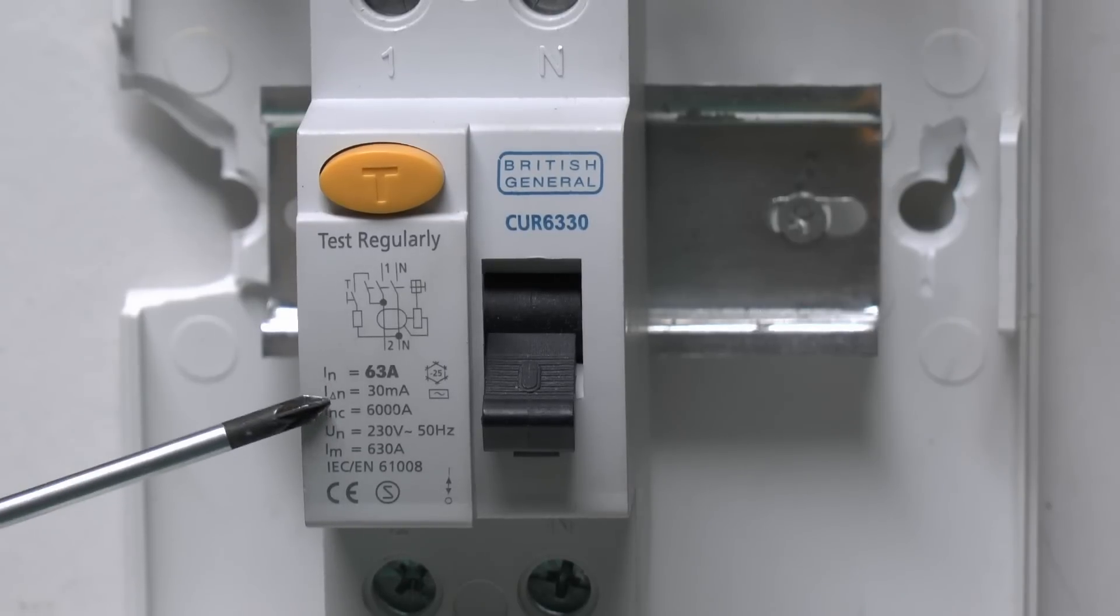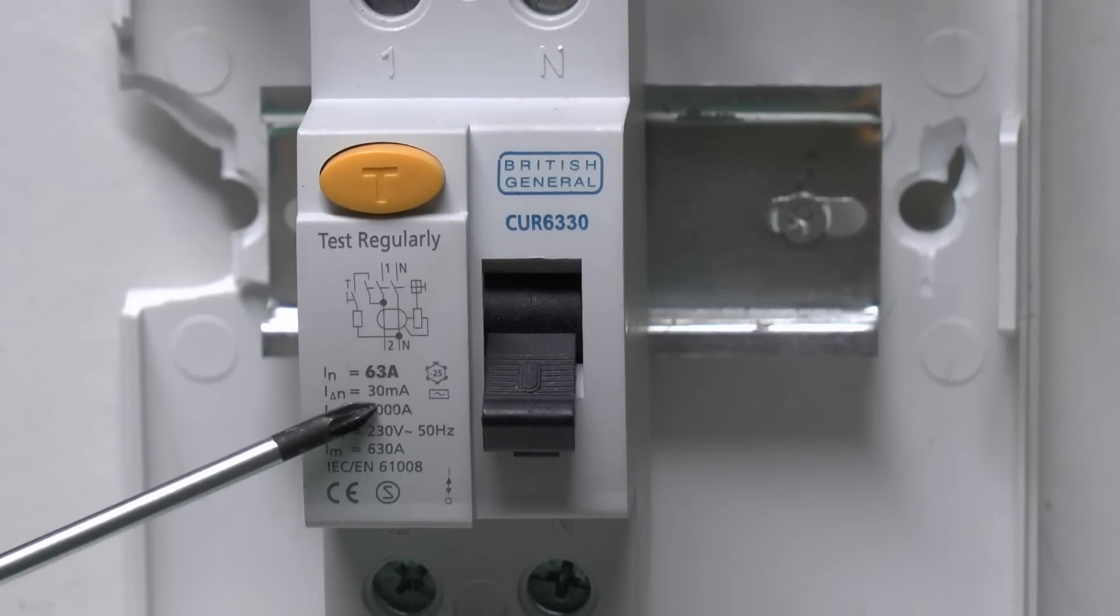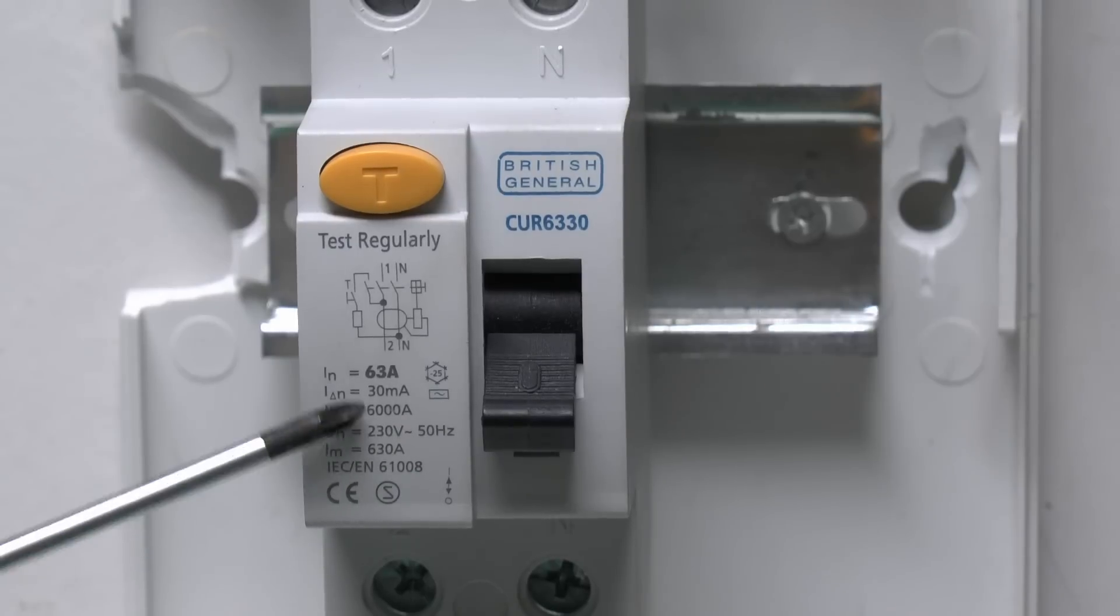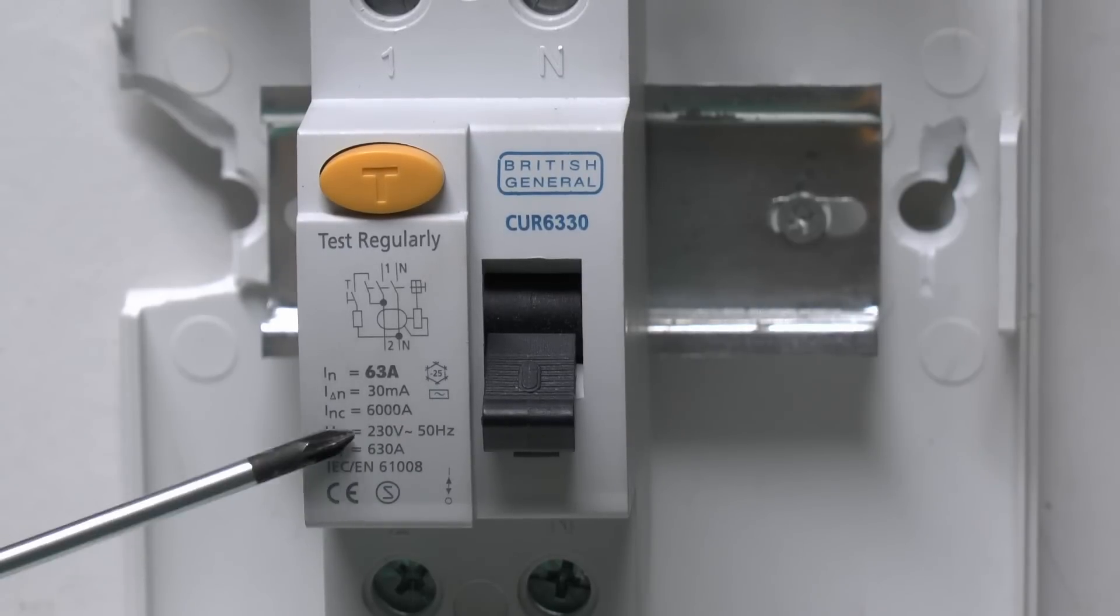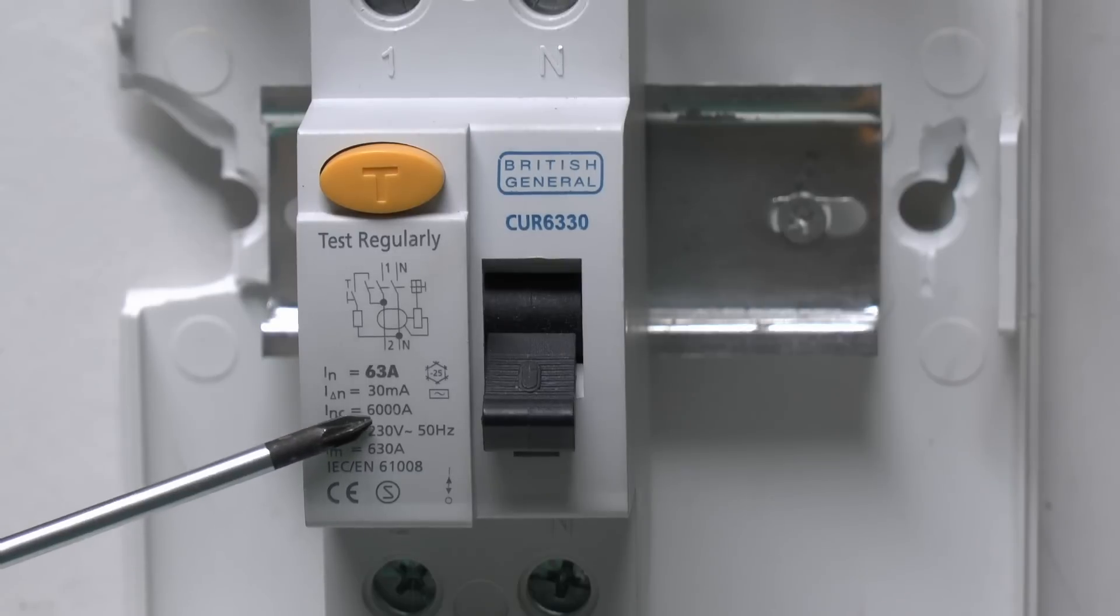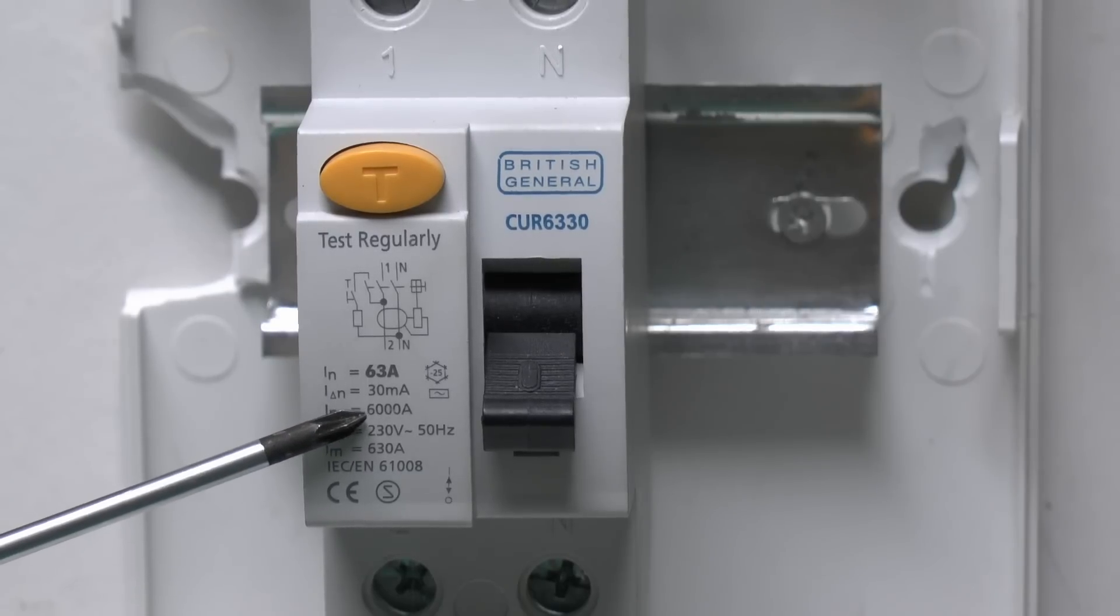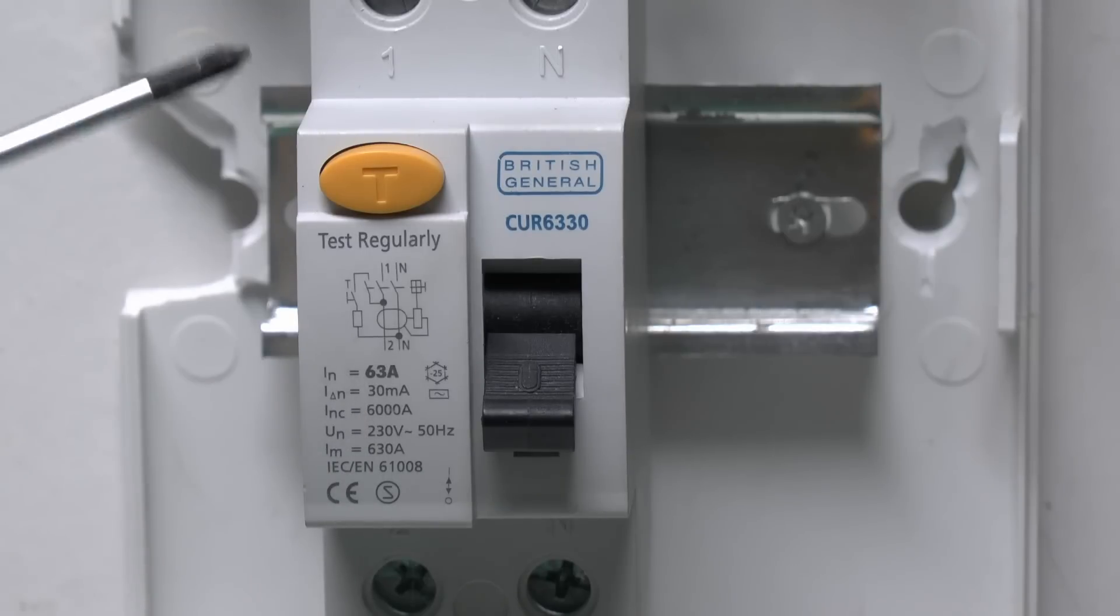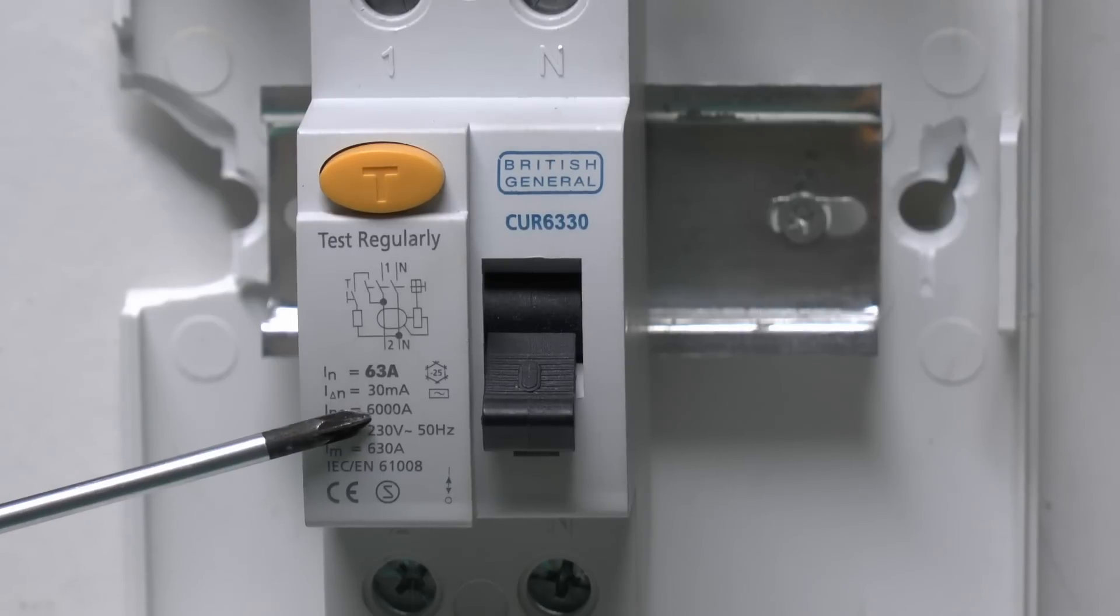Underneath that we've actually got the tripping current, so in this case 30 milliamps or 0.03 amps. Further on then we've got this rating here of 6000, which is actually the breaking capacity, so in the event of a fault between line and earth, that's essentially the maximum fault current that this thing is designed to disconnect.